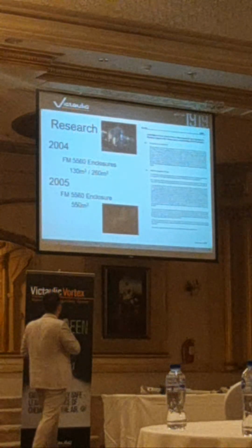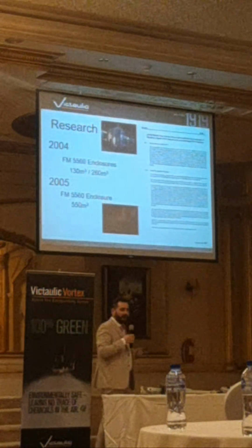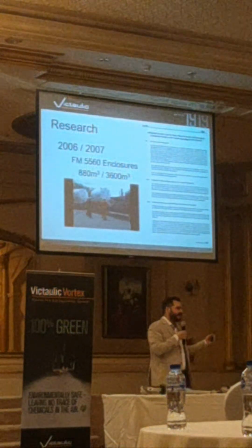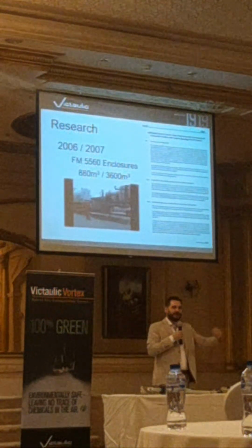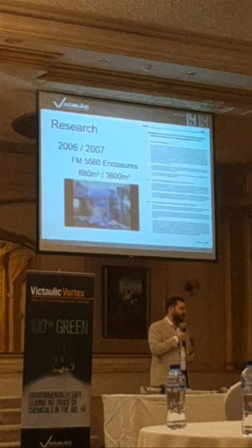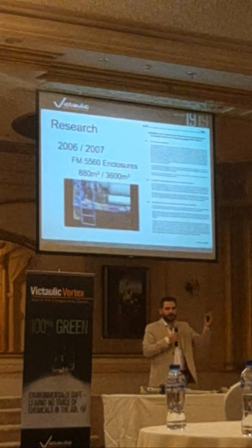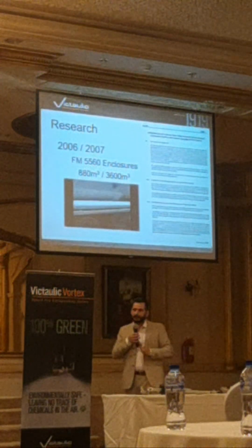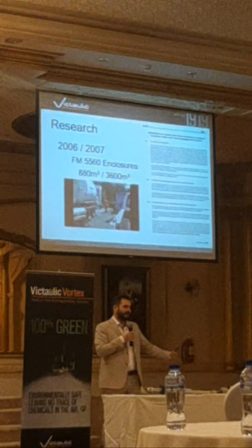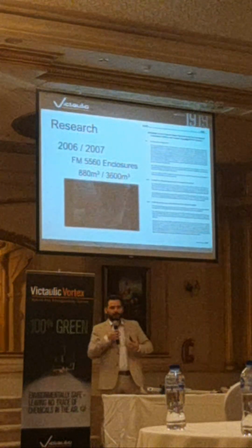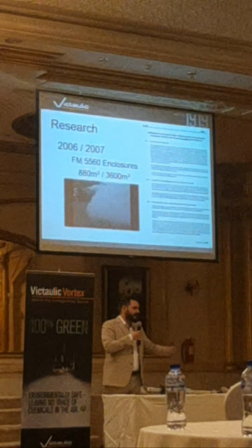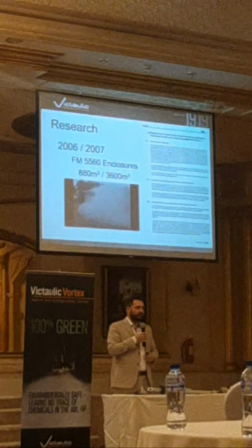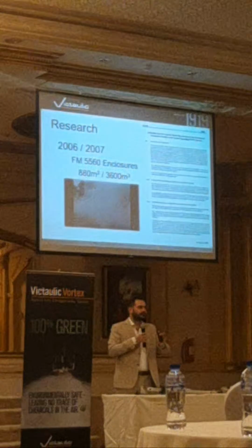What we originally did in the system is work from 130 cubic meters up to 3,600 cubic meters, and we saw that the bigger the volume, the more nitrogen and water you need. This was linear. So even though FM says you cannot extrapolate over that amount, you can work locally to have multiple zones and work within that scope.